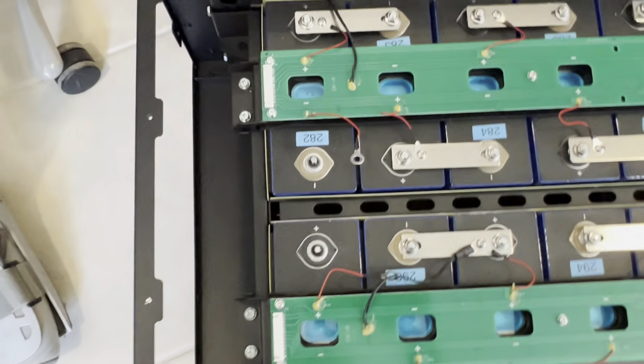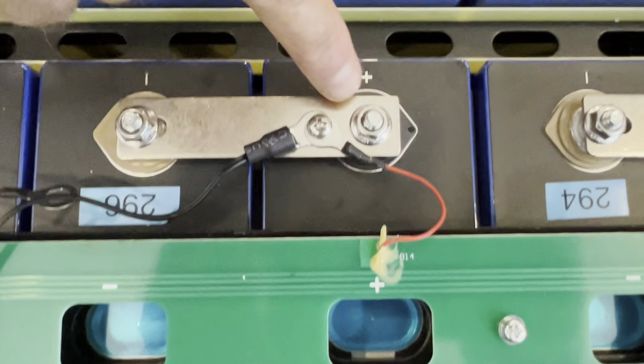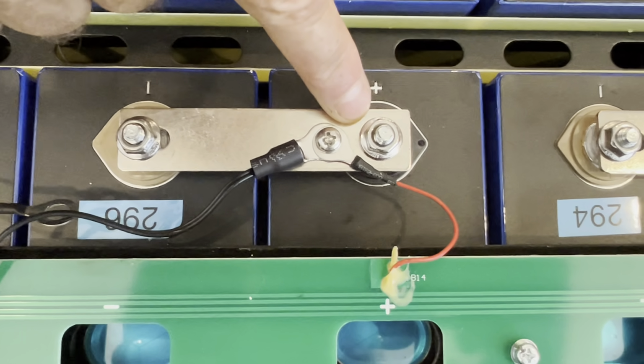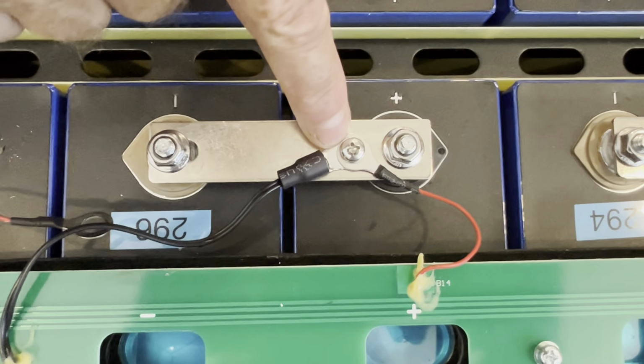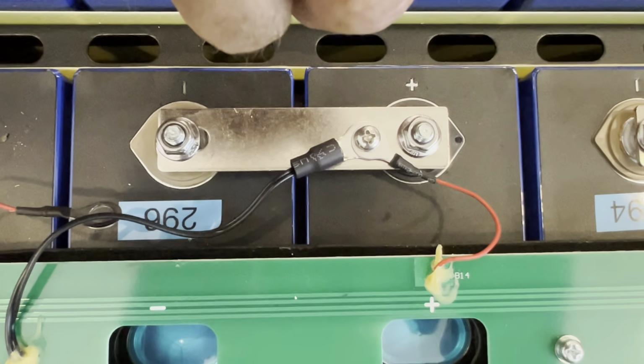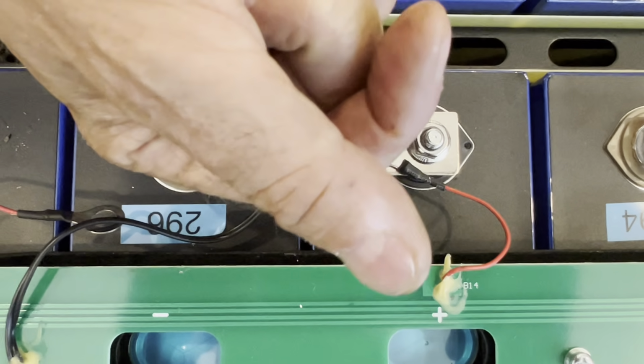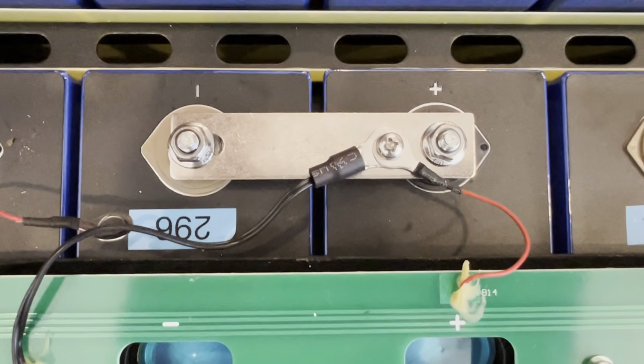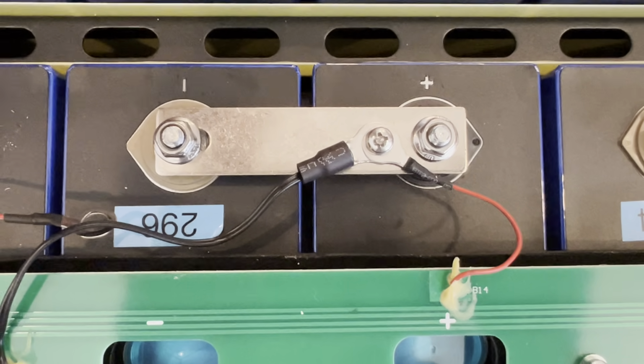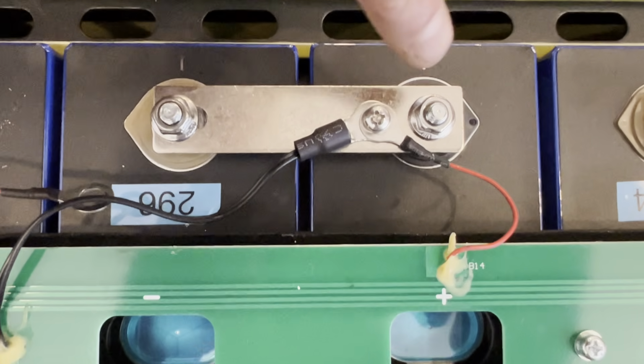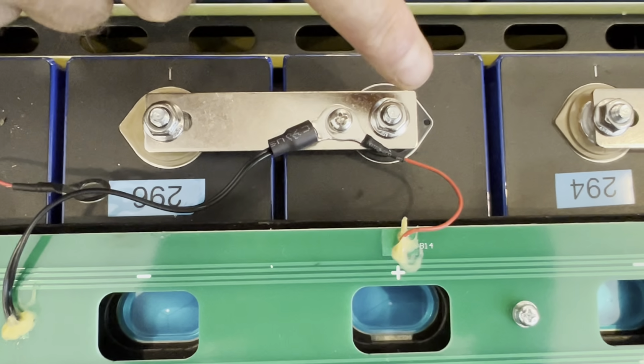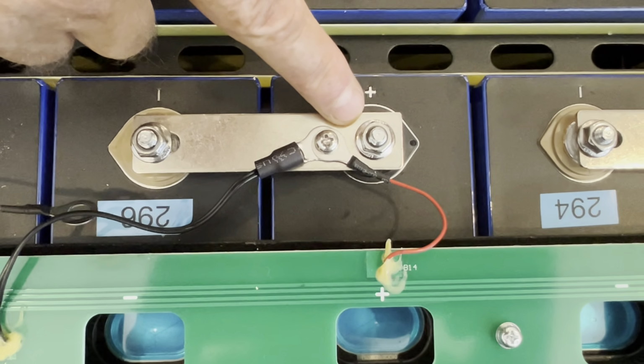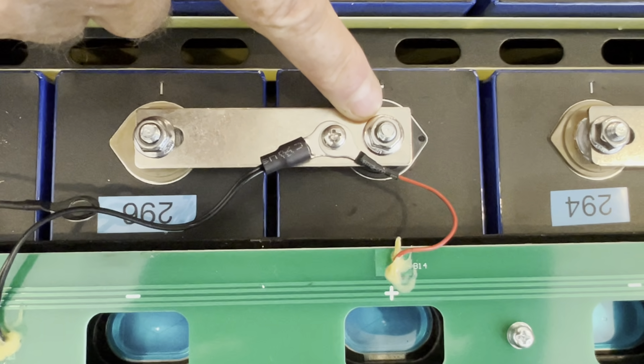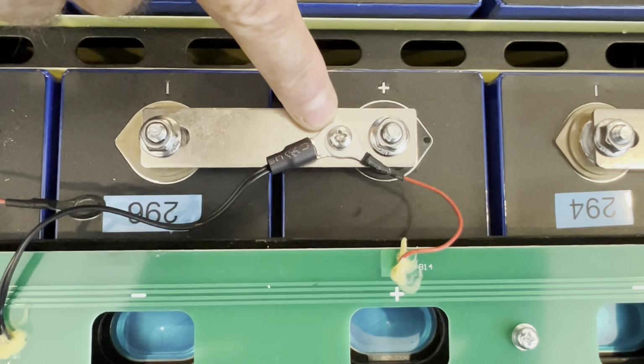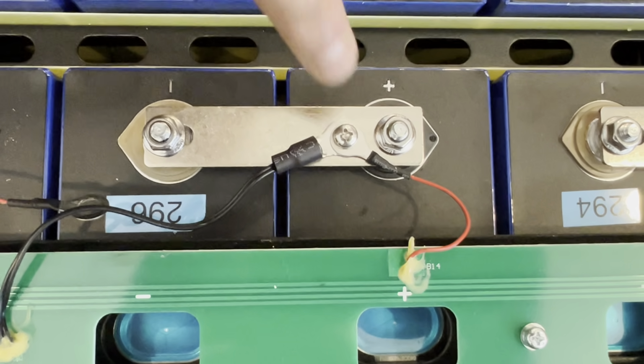If you put a ring terminal or a washer between the serrated nut and the bus bar, that serration will tighten onto the ring terminal but not onto the bus bar, and the whole thing can turn and loosen over time through hundreds and thousands of heat cycles. For this connection to be a permanent, forever connection, I want that serration biting into the bus bar, with my sensing wire in a separate location.